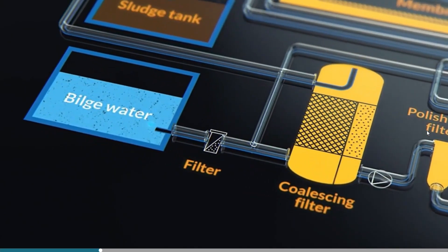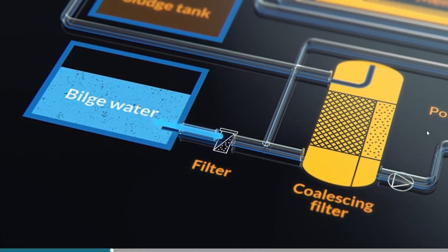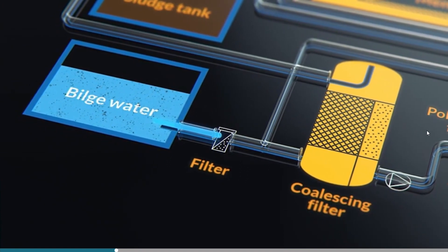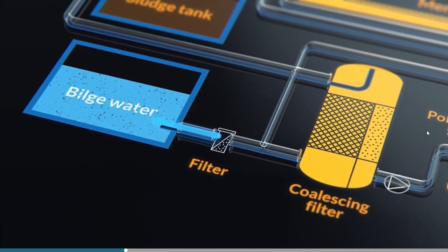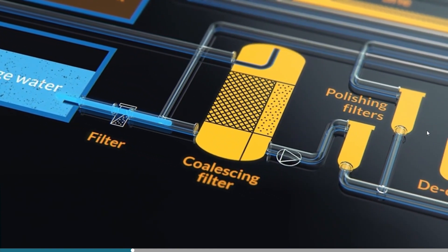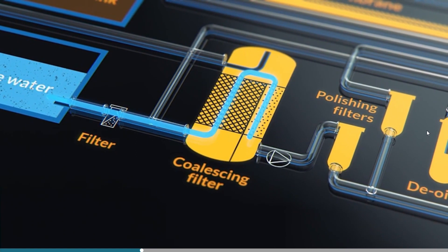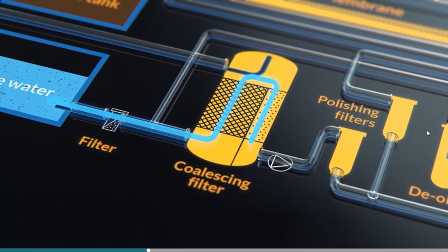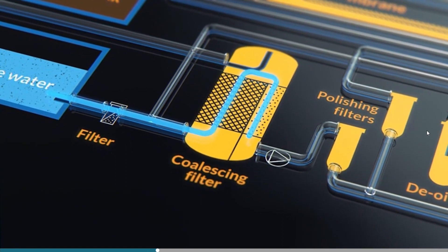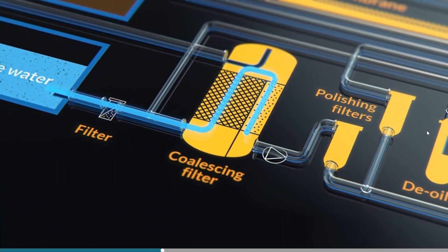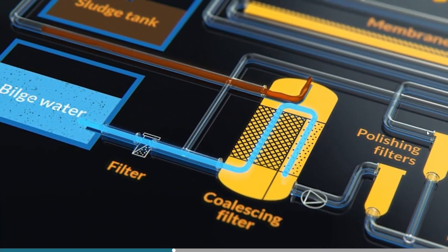Bilge water from the bilge tank is fed to a first stage via a filter. The filter prevents large solid impurities from entering the separator and causing blockages. In the first stage, the bilge water passes through a coalescing filter, where small oil droplets stick to the coalescing mesh. As the small droplets accumulate, they join together, coalesce, and then become buoyant enough to float off to the top of the first stage, from where they can be discharged to the sludge tank.